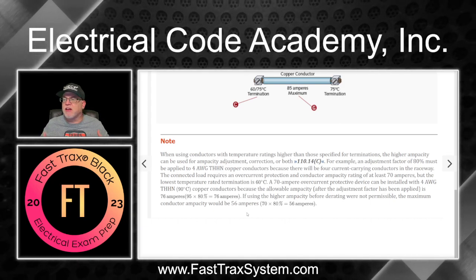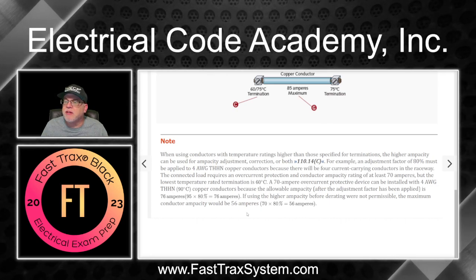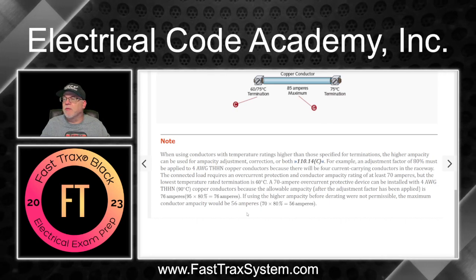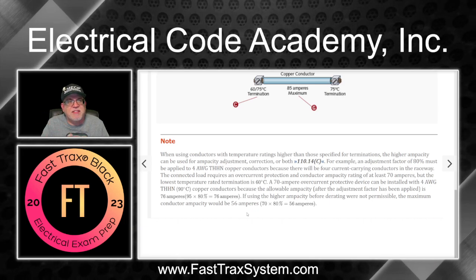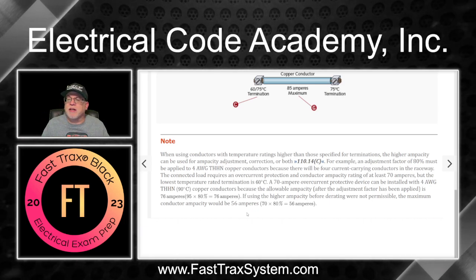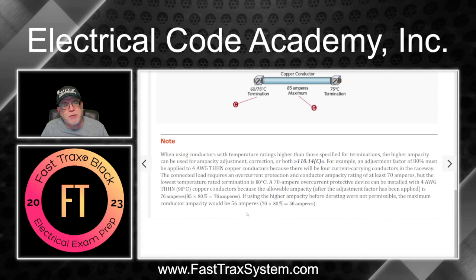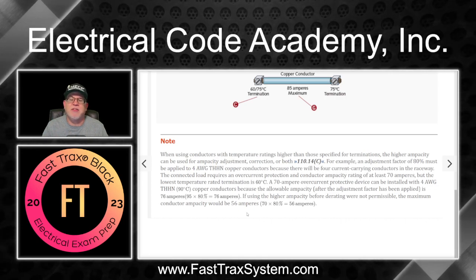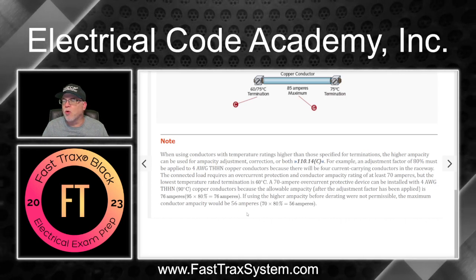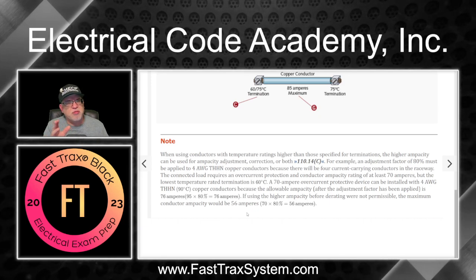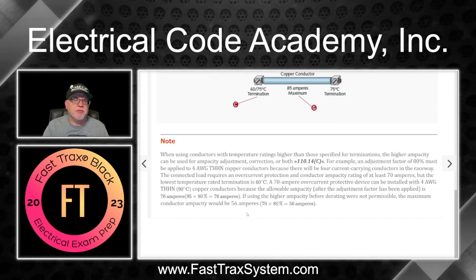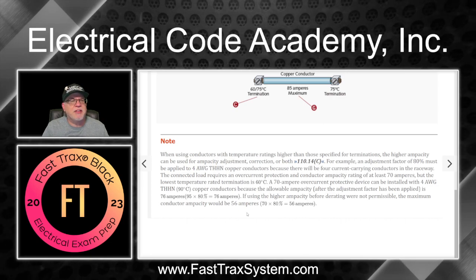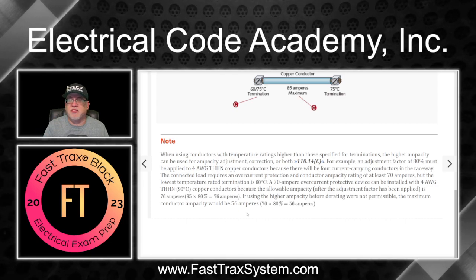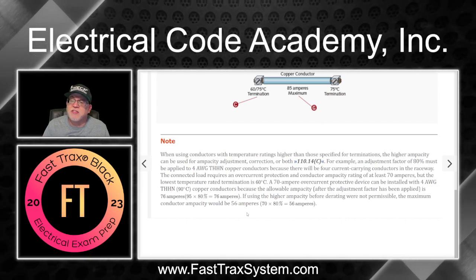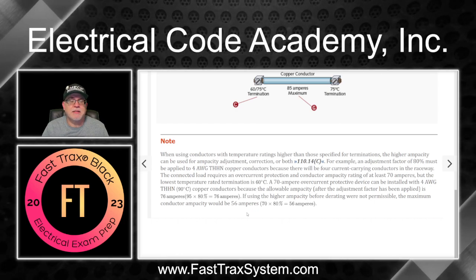And if you already had a specific load you needed to achieve, then again, we need to get at least 70 amps out of this example. That's not going to work. That means that 4 gauge is not going to be adequate, and I would have to increase in size. Since 3 is kind of rare, I would probably have gone up to a 2. I guess you can find 3, but I would have had to do the math over again and see if it's adequate to handle the 70 amps. Okay, that type of thing.